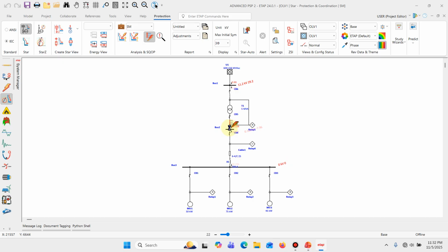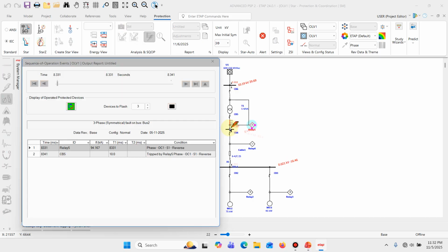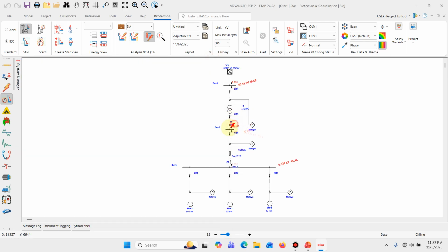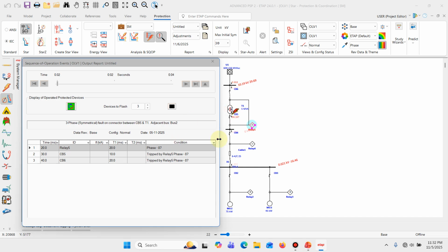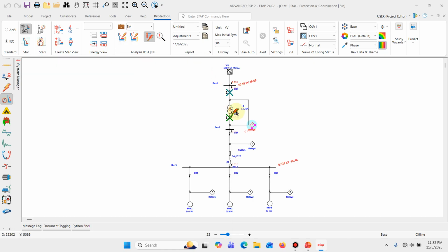Let's have it over here. Okay. And let's have it on the transformer. Okay, in this case, the differential protection kicked in, 87, instead of overcurrent protection, because the transformer is being protected by a differential protection scheme. Now, in this case, can we say that this system is properly protected and coordinated? Looks good, right?